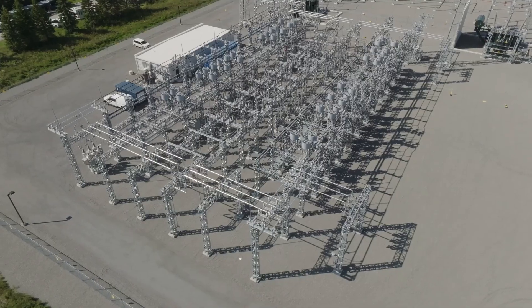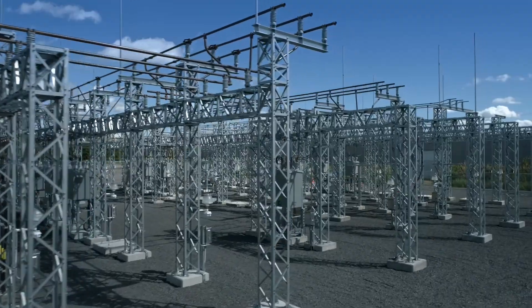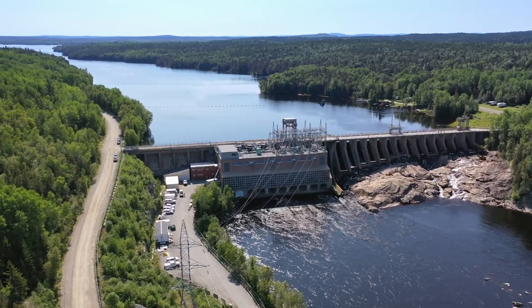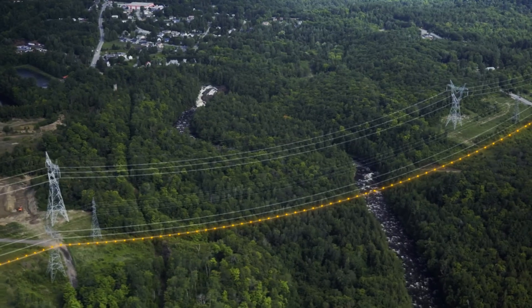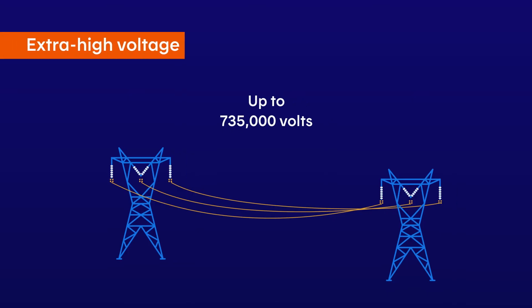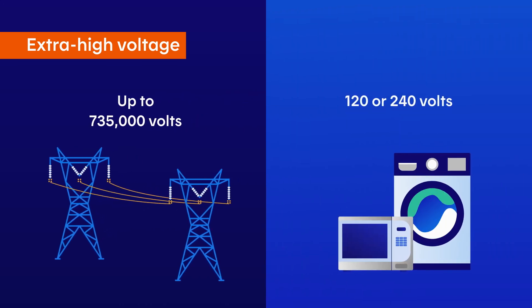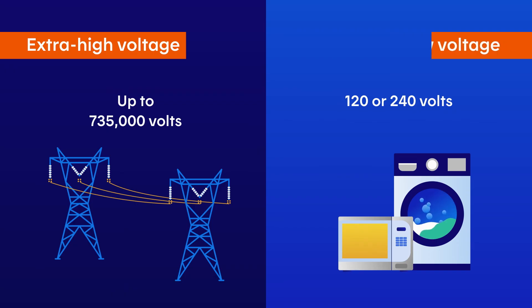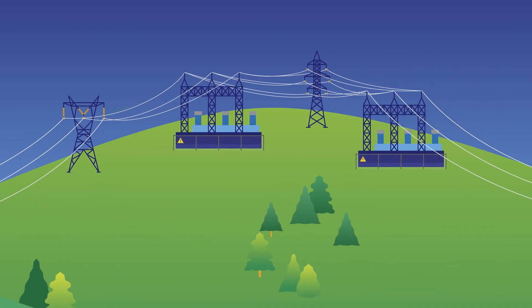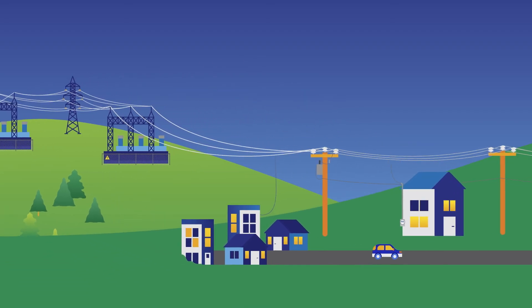The substation's main role is to raise or lower the voltage level of the electricity before it reaches our homes. It also directs the electricity by determining the route it will take to reach its destination, and it protects the grid. The voltage varies as electricity makes its way from the generating station to our neighborhoods. Over long distances, the voltage can reach up to 735,000 volts — that's extra high voltage. But at home, our appliances and devices operate at 120 or 240 volts, which is low voltage. On its journey, the electricity stops at several substations and changes voltage, adjusting as it moves from the generating station to our outlets.